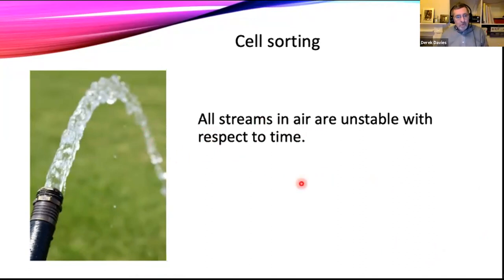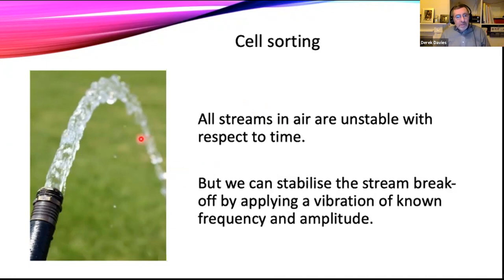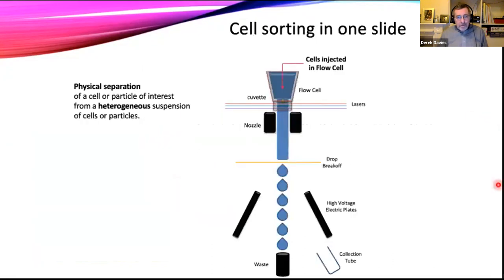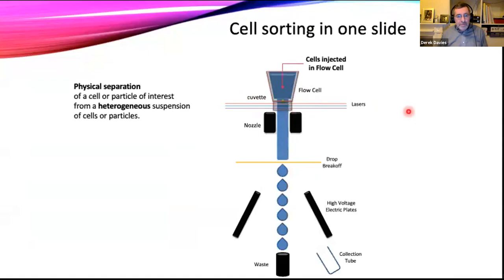Our streams are unstable — they're going to break up into droplets. If you vibrate a hose, the break-off stabilizes. We can stabilize that break-off by applying a known vibration — the number of times we move the hose per second and the amplitude. In essence, that's what we're doing on our flow sorter. This is cell sorting in one slide: we take our cells, inject them into a flow cell, they go through one or more laser beams, and as they go through those laser beams we get fluorescence emitted and capture the fluorescence characteristics of that cell.